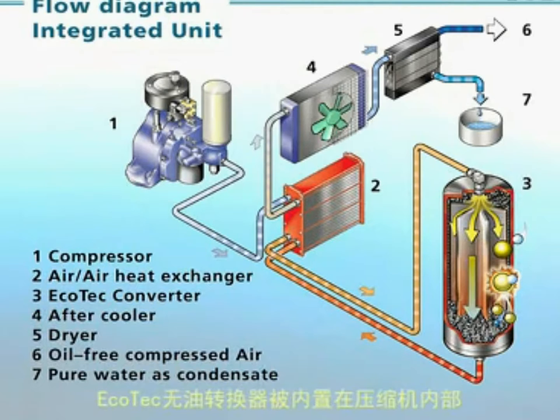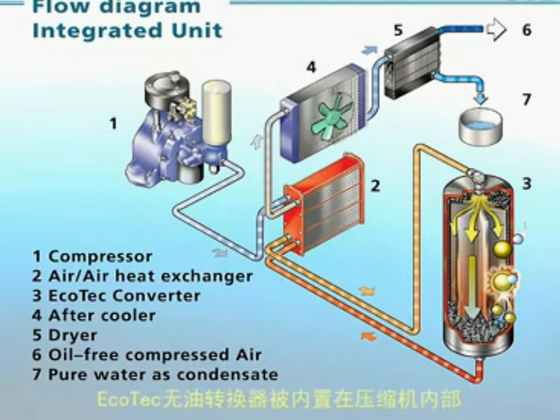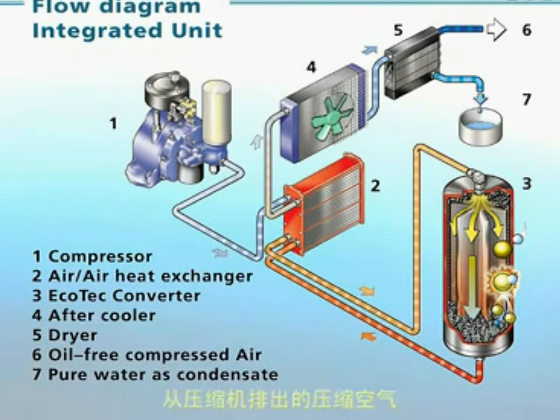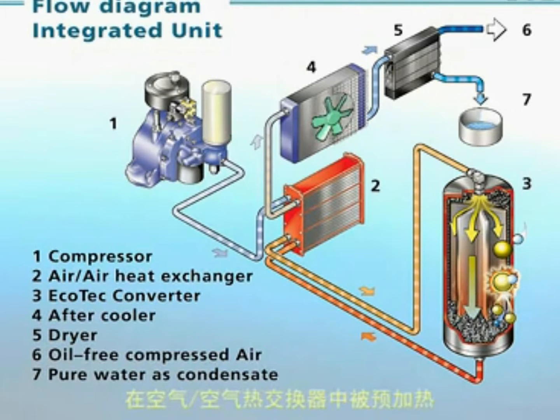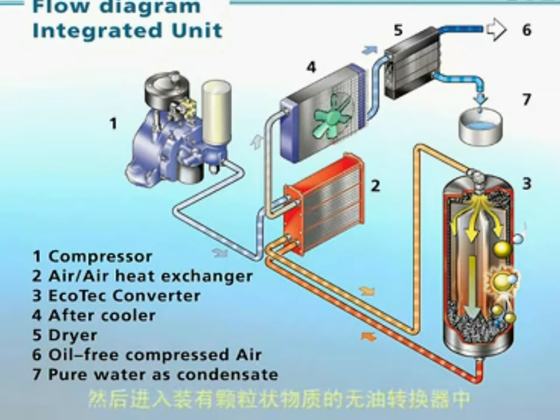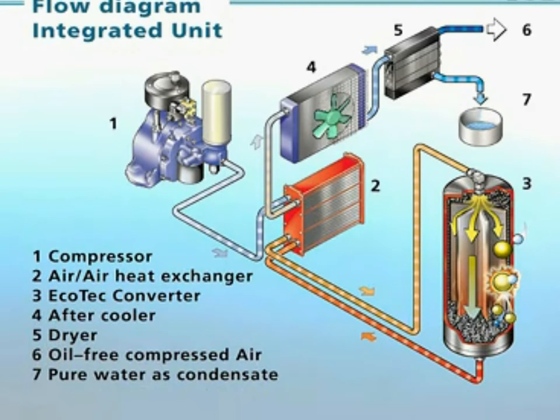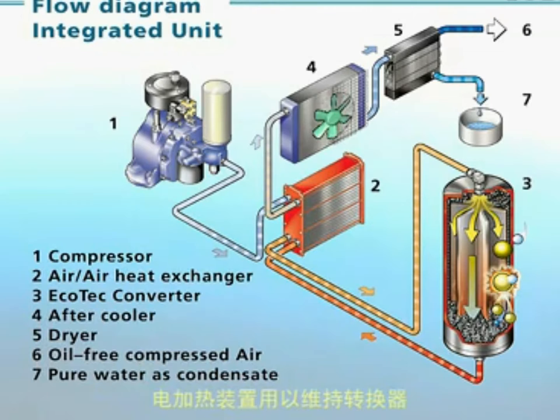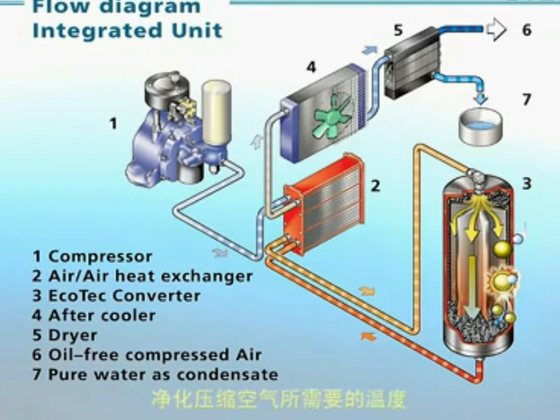The Ecotec Converter is installed right into the compressor unit. The compressed air coming out of the compressor is preheated in the air-air heat exchanger and then flows into the converter, which is filled with catalyst. An electrically operated heater maintains the converter at the operating temperature required to purify the compressed air.